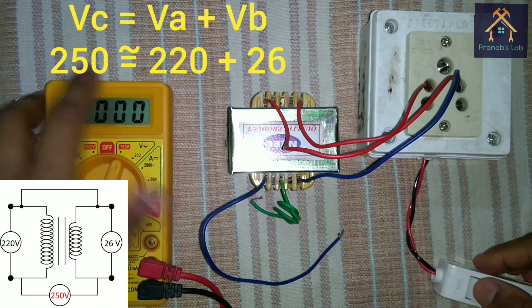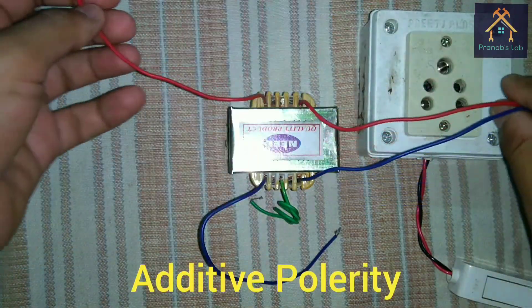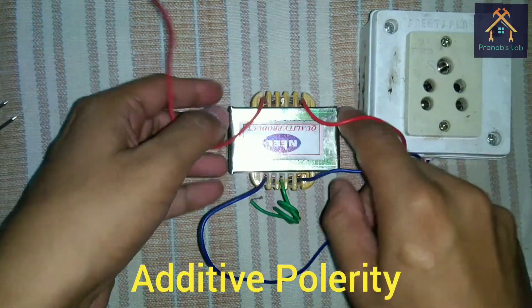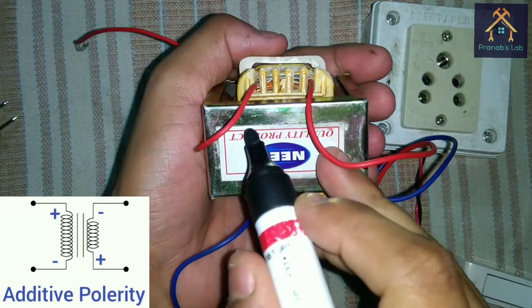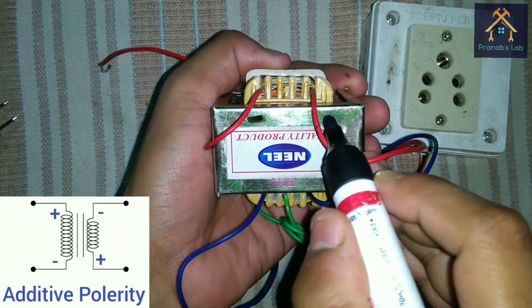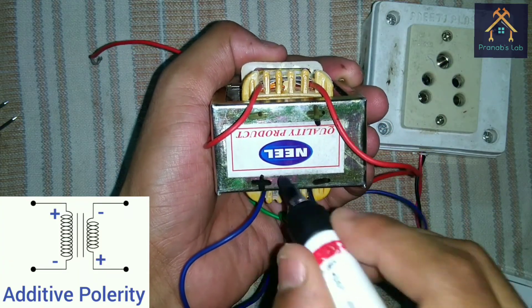From this test, we can conclude that this transformer is in additive polarity. And we can mark the transformer like this: negative, this is positive. Again, this is negative. And this is positive.